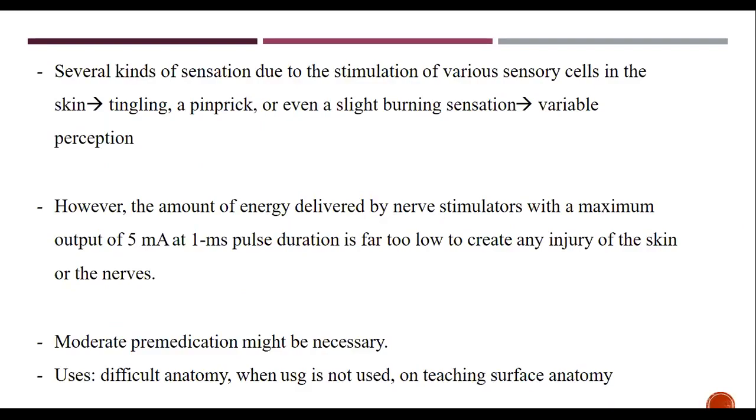Several kinds of sensation can occur due to stimulation of various sensory cells in the skin. It can have tingling, a pinprick, or even a slight burning sensation. However, the amount of energy delivered by nerve stimulators with a maximum output of 5 milliampere at 1 millisecond pulse duration is far too low to create any injury to the skin or the nerves. So it is very safe. Moderate pre-medication might be necessary. Uses are for difficult anatomy when ultrasound is not used, and for teaching surface anatomy.